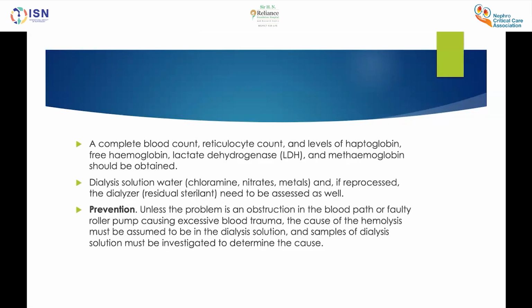And how do you prevent this? Unless there is an obstruction in the blood path or a faulty roller pump that can cause excessive blood trauma, the cause of hemolysis must be assumed to be in the dialysis solution, and samples of dialysis solution must be investigated to determine the cause.